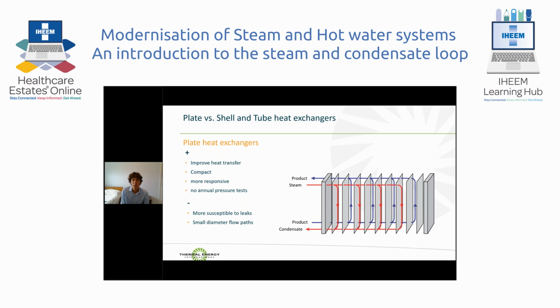If we use brazed plate heat exchangers or welded plate heat exchangers, that eliminates the gasket leak problems, and they're very suitable for steam applications. One thing to bear in mind when specifying plate heat exchangers is that increasing the pressure drop across the heat exchanger can significantly reduce the cost of the heat exchanger and also improve its heat transfer potential by having more turbulent flows.